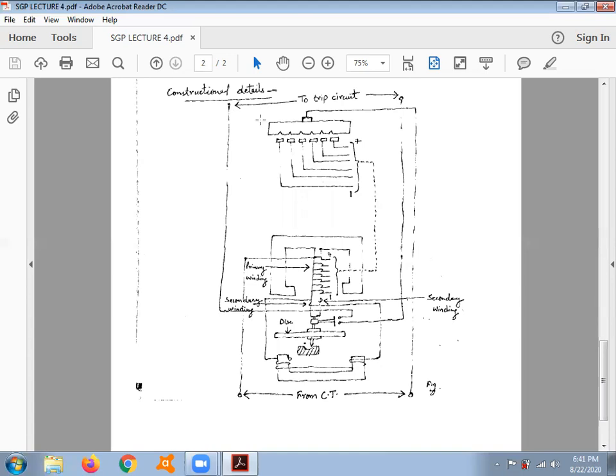At the top end there is a plug setting multiplier, and there are 7 wires which can be taken out of it. The job of the plug setting multiplier is that it sets the value of current at which the relay has to operate - like it can be 100 amperes, 50 amperes, 75 amperes, 200 amperes. At whatever value the relay will sense and close the contact of the trip circuit, that value is set by this multiplier - the plug setting multiplier.